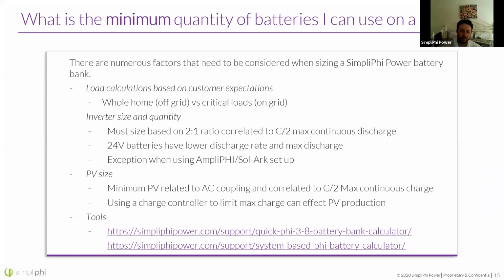Now, when using the AmpliPHI battery, our newest battery, at least when it comes to what it can pair with, so currently it's just the Sol-Ark, soon it'll be other inverters, you're not required to follow this ratio as far as sizing goes. So you can have 2 batteries on a 12 kilowatt Sol-Ark. That is okay, and that is acceptable sizing, as the AmpliPHI battery has that communication line and actually has the ability to ensure that the battery does not over discharge.